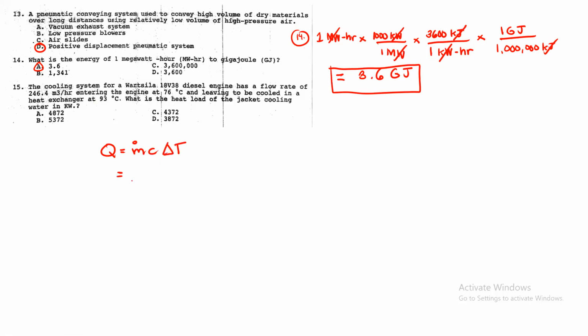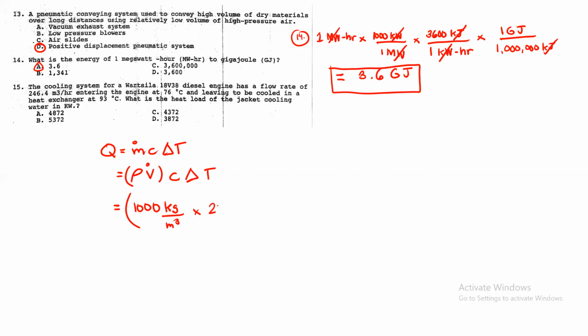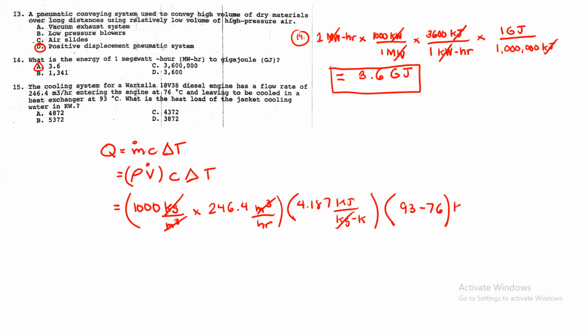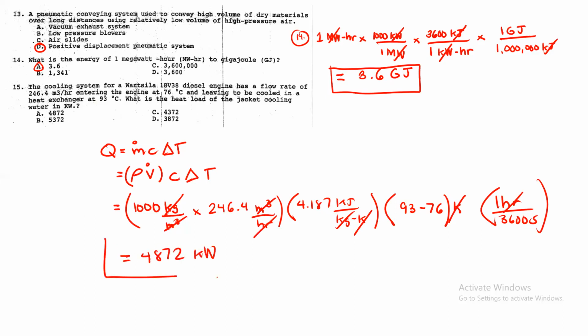So, mass flow rate yan. So, mass flow rate natin is density times volume flow rate, times C delta T. So, substitute. So, 1,000 kilograms per cubic meter. Then, volume flow rate. So, ilan yung volume flow rate natin? So, volume flow rate natin dito is 246.4 meter cube per hour. So, makancel this meter cube. Then, times C, 4.187 kilojoules per kilogram Kelvin. Makancel this kilogram. Then, change in temperature is 93 minus 76. So, change yan, no? So, pwedeng Kelvin na rin yan. Then, kilojoules per hour yung matitira. So, convert natin 1 hour per 3,600 seconds. So, kilowatts na yung matitira dito. So, sagot dito is 4,872 kilowatts. So, the answer is letter A.